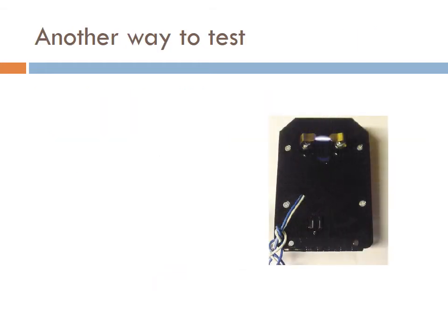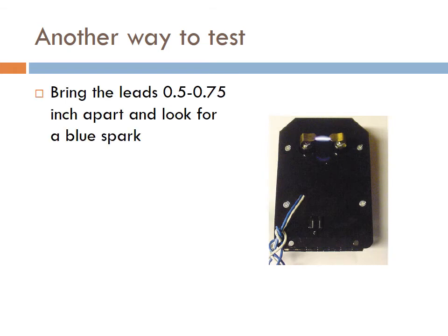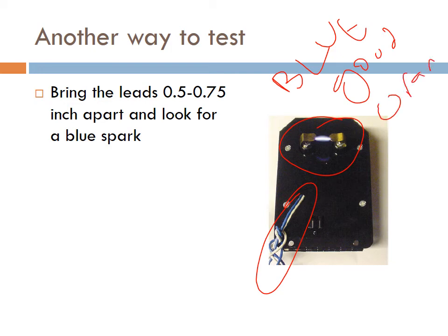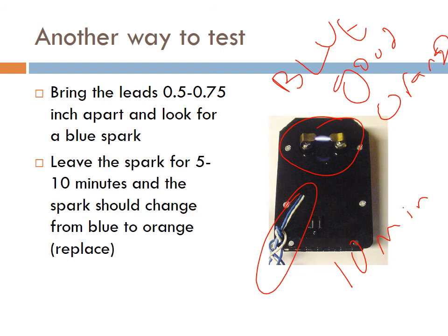Another way to test a transformer, this one has less conviction and is very subjective to your conditions, says you should bring the prongs together within half an inch, power the transformer, and look for the color. It should be blue. Blue means good. If it's orange, then it's not giving you enough power. But again, it's very subjective, and you have to leave it on for 10 minutes. It might start as blue, then as it heats up, it might go back to orange. Leave the spark for 10 to 15 minutes to check. If it changes, then replace. It's very difficult to judge by color, so I really don't recommend this way.